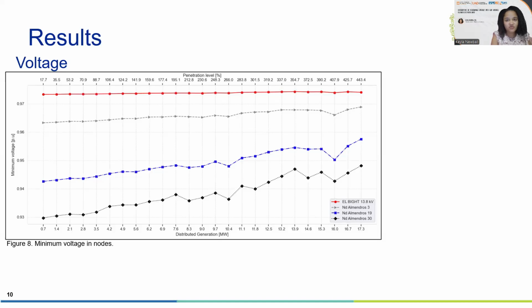Okay, so now I'm going to expose the results. The data is in form of graphics to summarize the findings for each of the performance index. The first one is voltage. So as expected, when there is integration of renewable energies, there is voltage rise. So this image is the minimum voltage registered in some nodes for each penetration level. And here we can see that the nodes at the end of the circuit are near minimum voltage regulation without the penetration of renewable energies. And when there is integration, the voltage rises. So this is positive in this case.